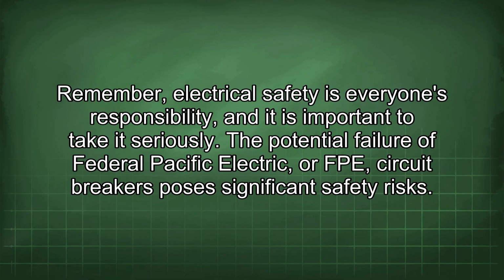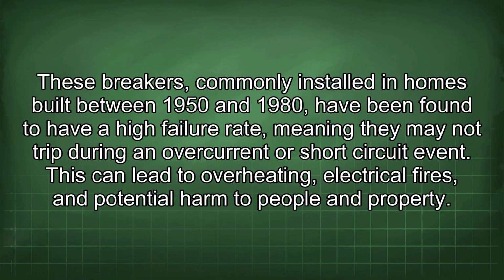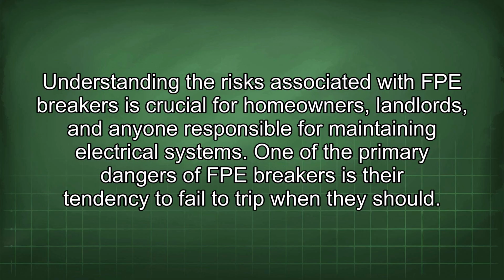The potential failure of Federal Pacific Electric, or FPE, circuit breakers poses significant safety risks. These breakers, commonly installed in homes built between 1950 and 1980, have been found to have a high failure rate, meaning they may not trip during an overcurrent or short-circuit event. This can lead to overheating, electrical fires, and potential harm to people and property. Understanding the risks associated with FPE breakers is crucial for homeowners, landlords, and anyone responsible for maintaining electrical systems.